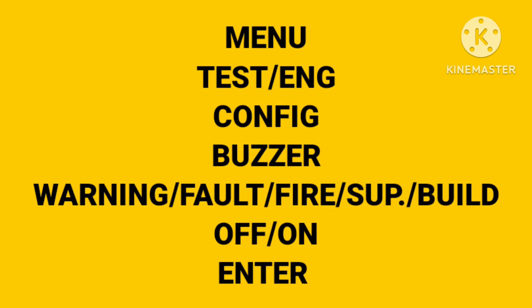For that, first go to Menu, then Test, then Engineering and Config, then Buzzer. We have options: Warning, Fault, Fire, or Supervisory. If you need to turn off on fault, you can turn it off. If you only want the buzzer to sound on fire, you can set it to Fire and turn it on.